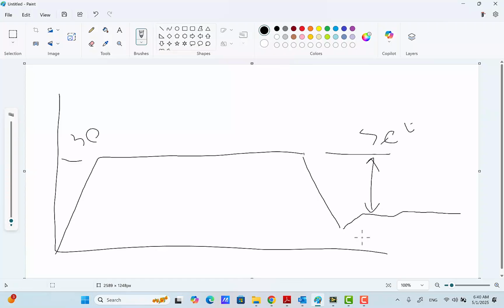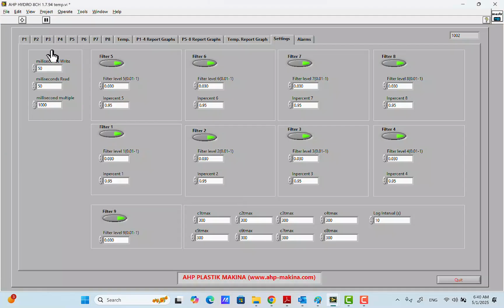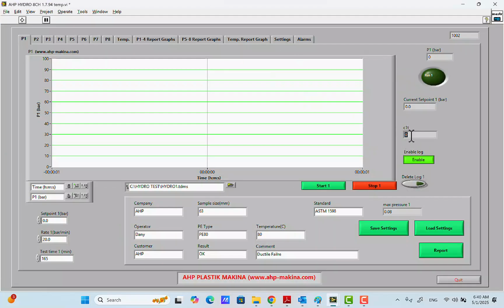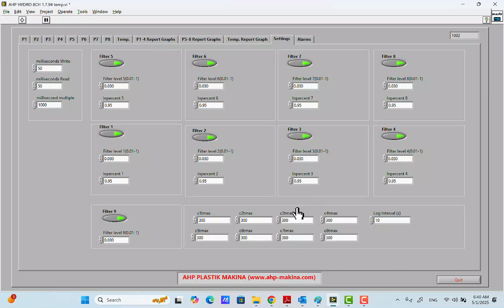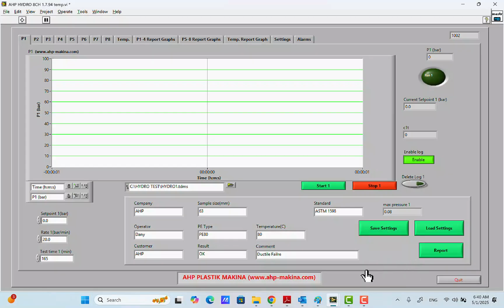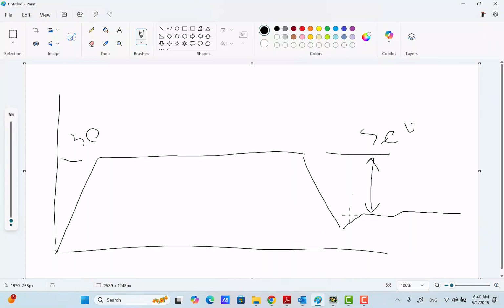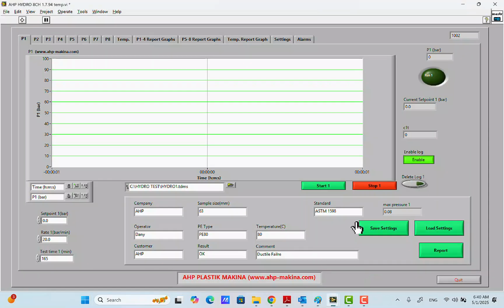In any such circumstances, C1T here will start counting up. When it gets to this maximum value and the pressure does not get to the set point, it will stop that line automatically. This is one important function for protecting the pump. The operator needs to check what happened that the pressure is not getting to the set point.